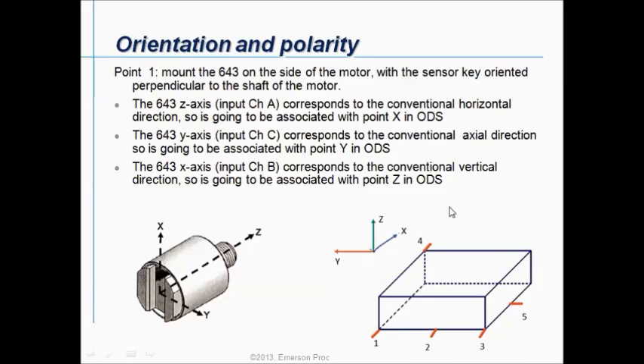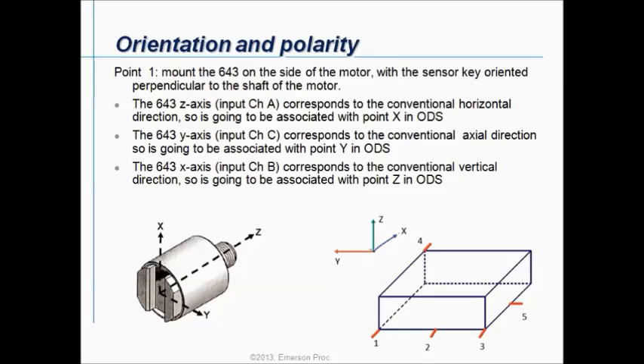If you have your ODS structure and you want to make an ODS structure on this block, I have pointed out 5 different points where I want to collect data. On an ODS job you can specify your axis — this is my X, this is my Y, and this is my Z. In the beginning, if you install your triax sensor in the horizontal radial direction and perpendicular to the shaft of the motor, the Z axis of the sensor — input A — corresponds to the conventional horizontal direction, so it is associated with point X in the ODS. The Y axis of the sensor — input C — corresponds to the conventional axial direction, so it is associated with point Y in the ODS.